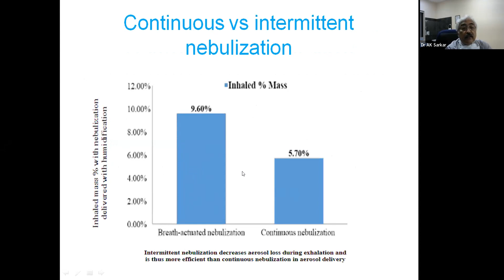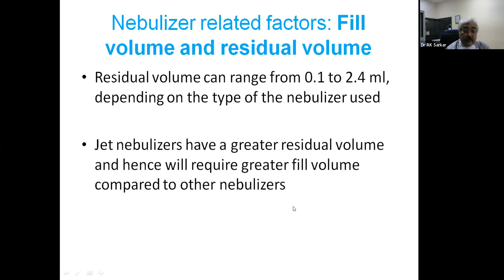Coming to fill volume and residual volume, this applies to your jet nebulizer. On the jet nebulizer chamber there is a line showing how much it has to be filled to get the maximum effect, and it is always between 4 to 6 milliliters. When you are using it, there will always be some residual volume, so you can't nebulize all the volume. But that doesn't apply to vibrating mesh or ultrasonic nebulizers, which can have a very low residual volume, 0.1, whereas in a jet nebulizer this could be as high as 2.4. Therefore, when using a jet nebulizer, always fill up to the maximum fill volume level so that you can deliver an adequate amount of drug into the system.